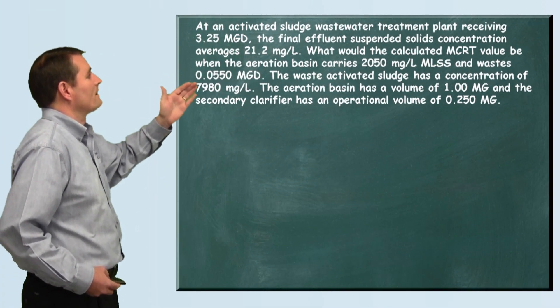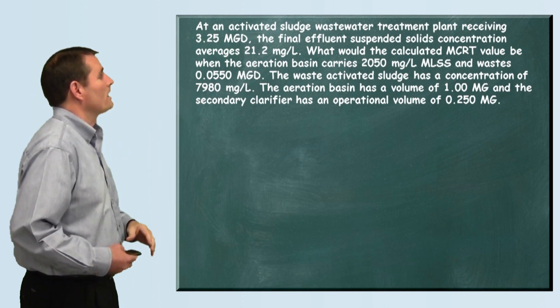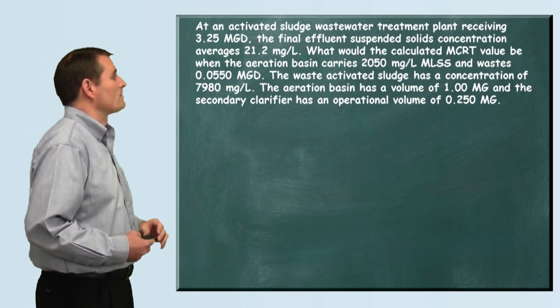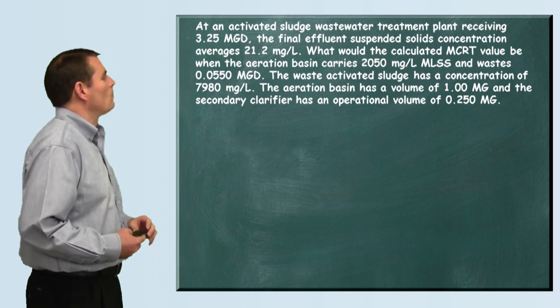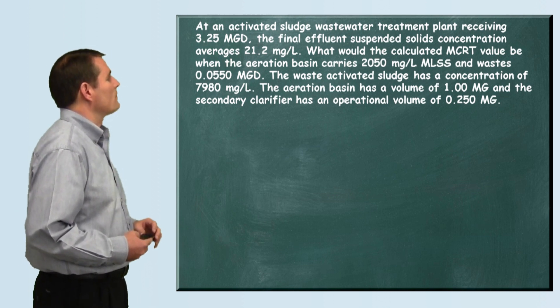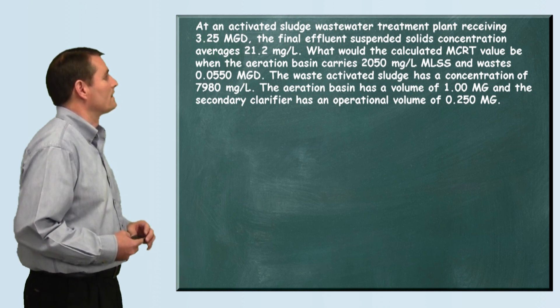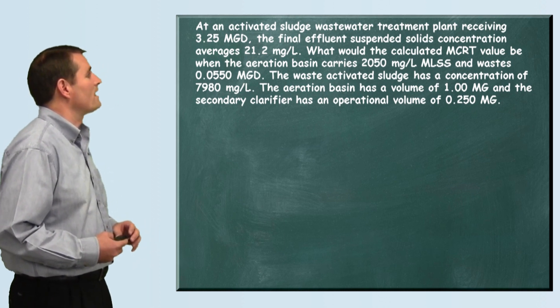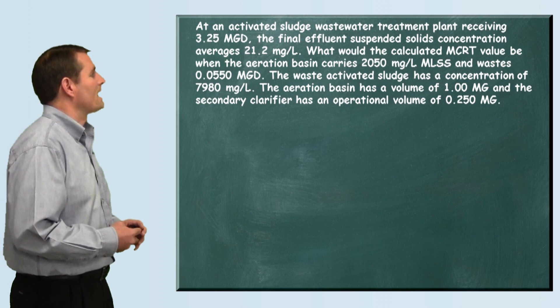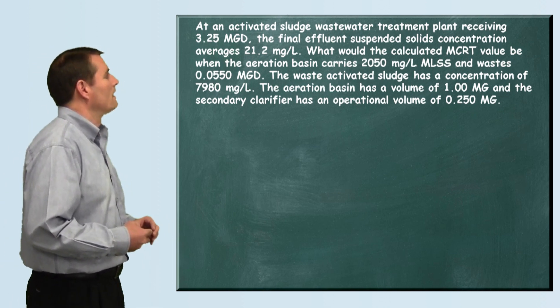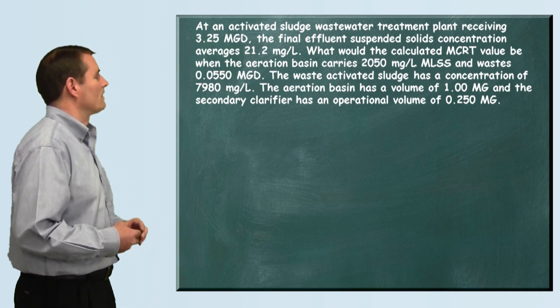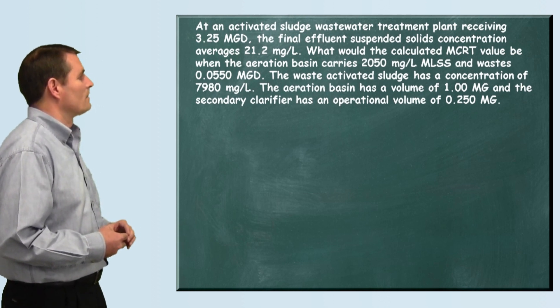The problem reads: at an activated sludge wastewater treatment plant receiving 3.25 million gallons per day, the final effluent suspended solids concentration averages 21.2 milligrams per liter. What would the calculated MCRT value be when the aeration basin carries 2,050 milligrams per liter of mixed liquor suspended solids and wastes 0.0550 million gallons per day? The waste activated sludge has a concentration of 7,980 milligrams per liter. The aeration basin has a volume of 1 million gallons, and the secondary clarifier has an operational volume of 0.250 million gallons.